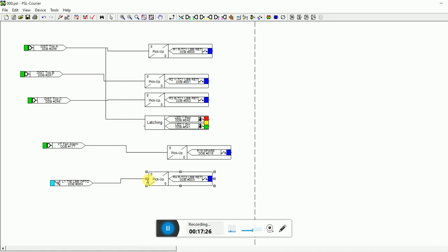So when my relay input L1, input 1, goes high, it will trigger this output 4 contact. Like that you can configure all the output contacts and LEDs for any Micom P442 or any Micom based relay by using this software.